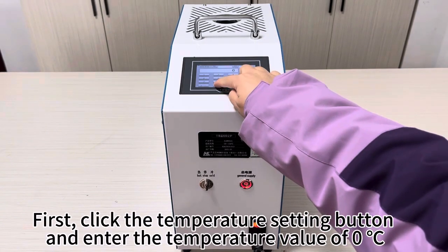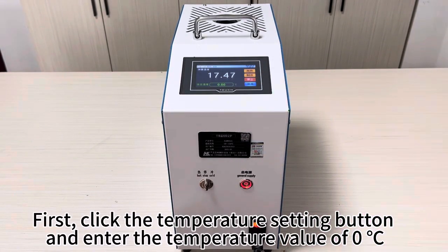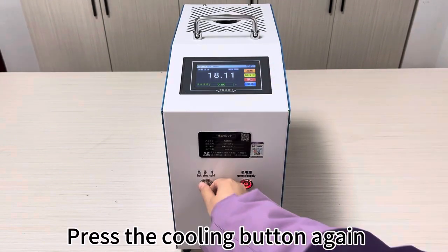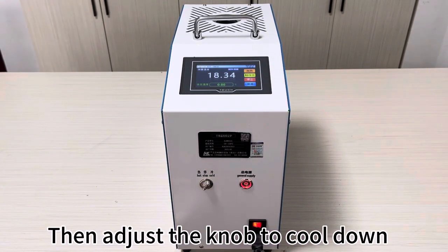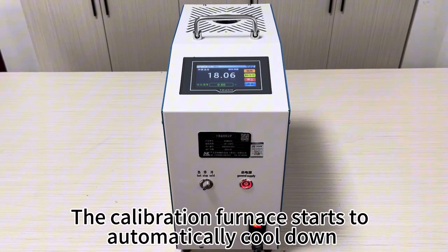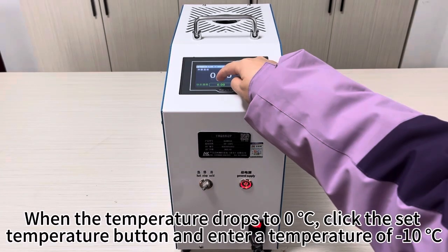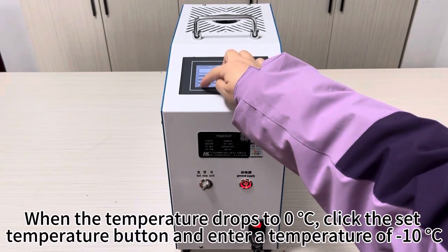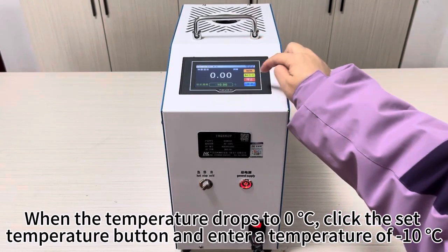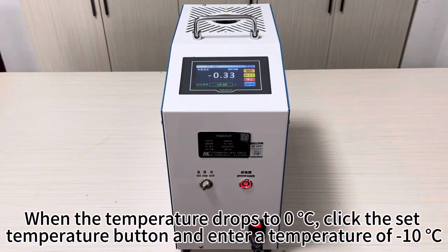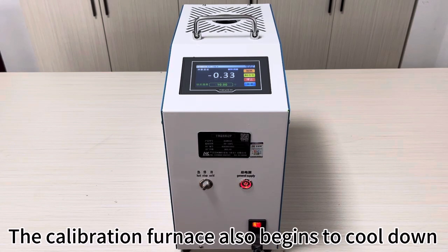First, click the temperature setting button and enter the temperature value of 0 degrees Celsius. Press the cooling button again, then adjust the knob to cool down. The calibration furnace starts to automatically cool down. When the temperature drops to 0 degrees Celsius, click the Set Temperature button and enter a temperature of -10 degrees Celsius. The calibration furnace also begins to cool down.